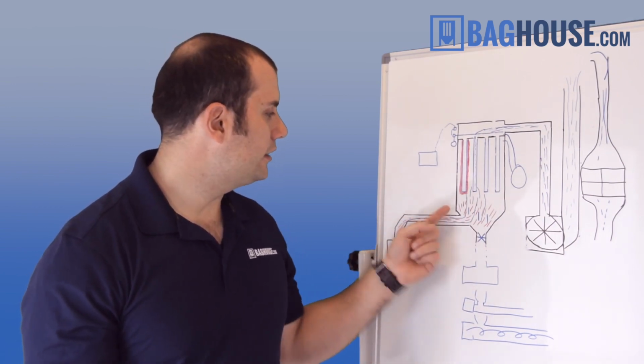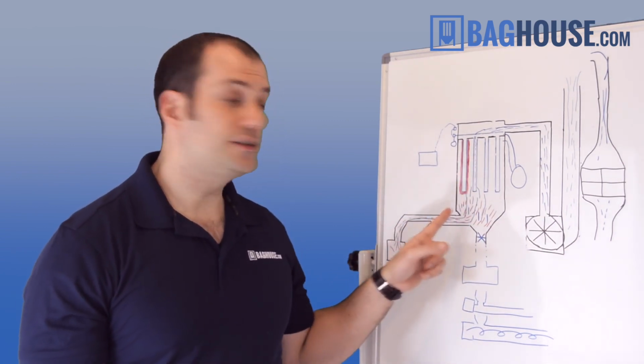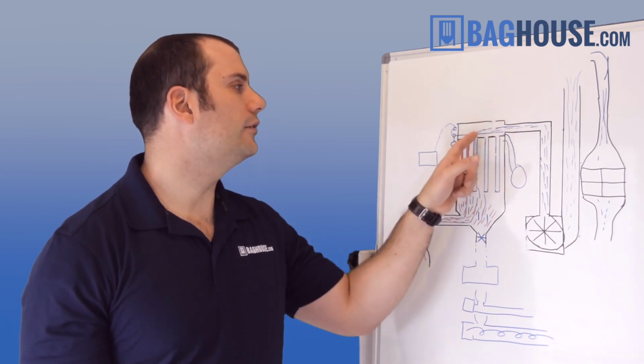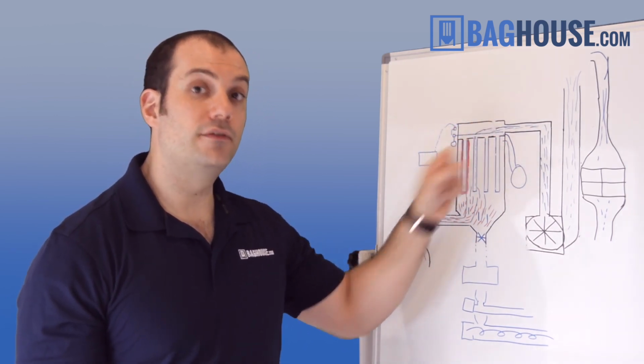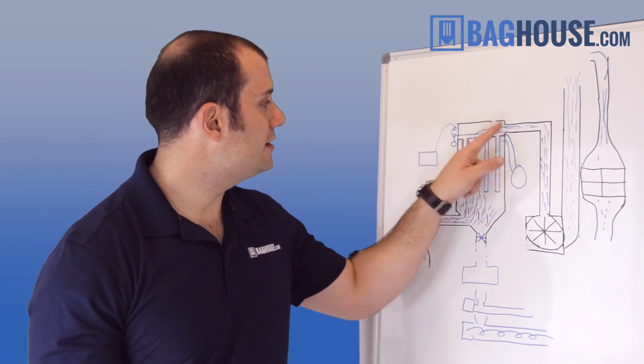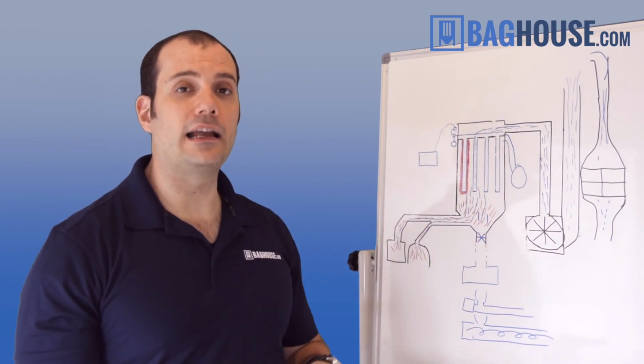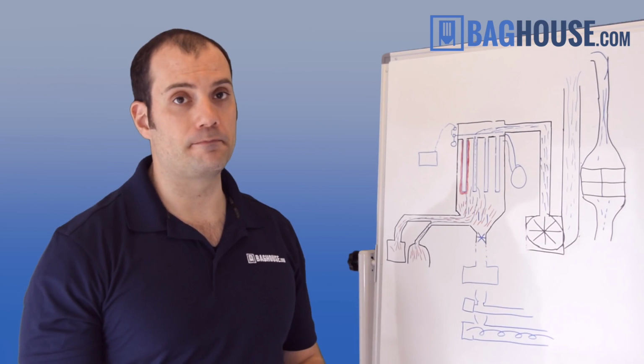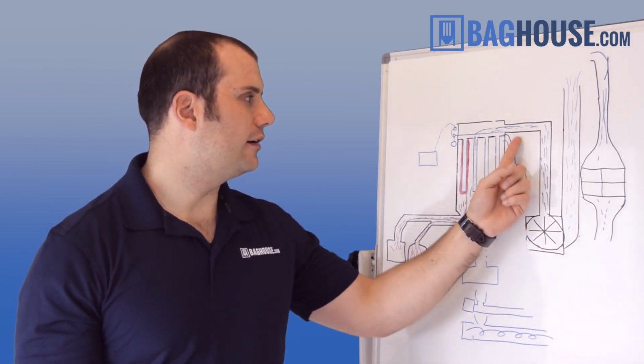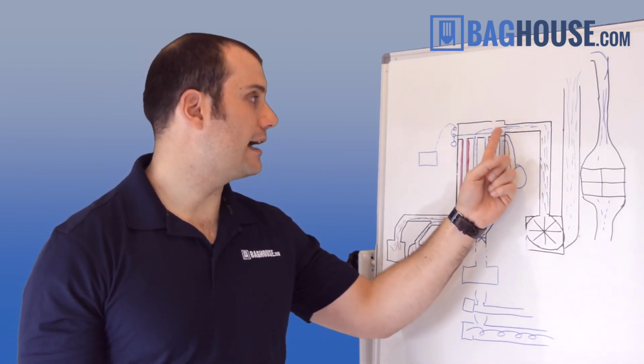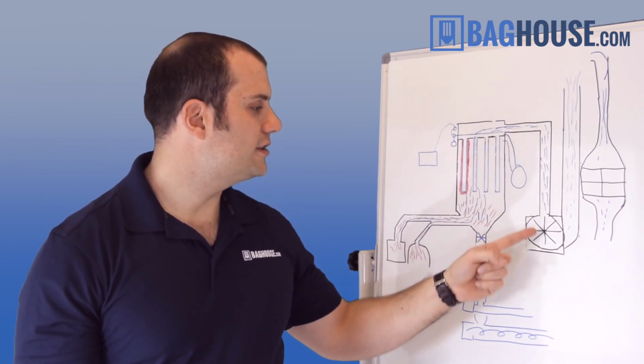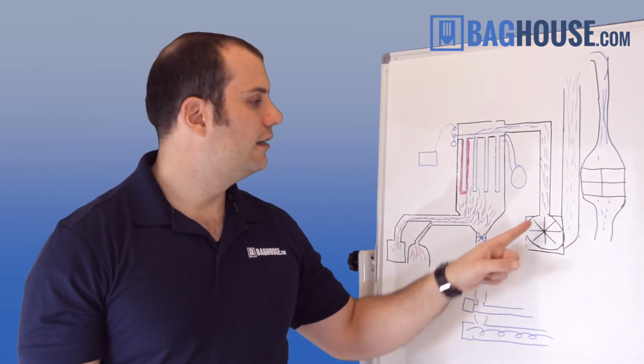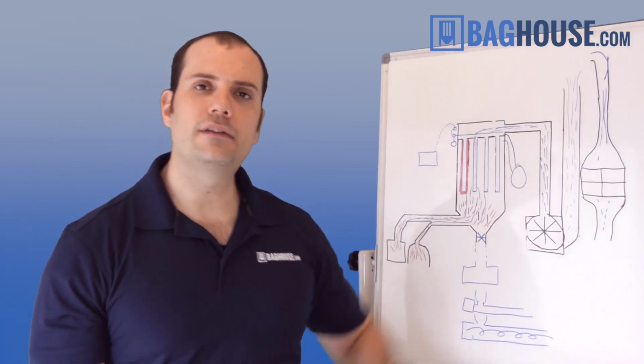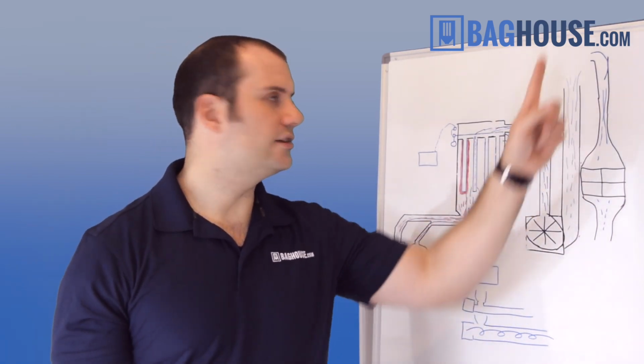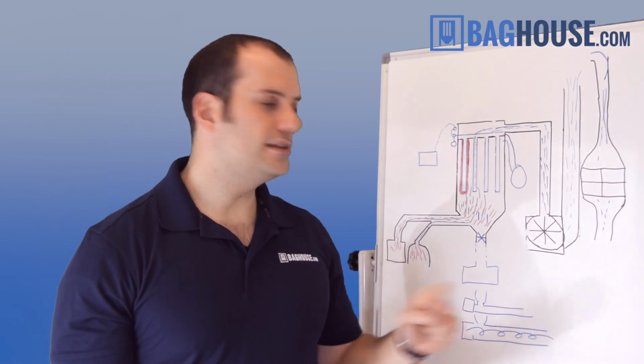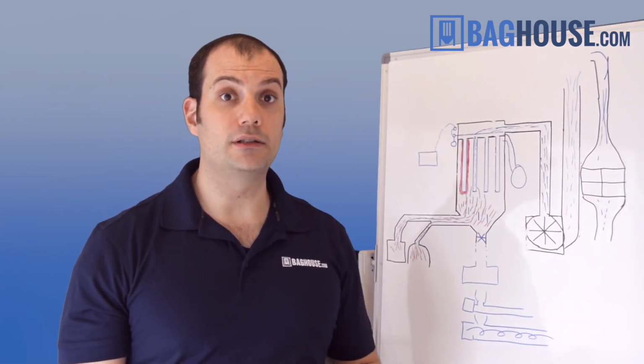Now, as the dirty air comes in, goes into the filters, only clean air comes up and out into this section up here, above the tube sheet. For that reason, we call this section of the dust collector the clean side of the Baghouse, or the clean air plenum. As we leave, we have our connecting ductwork, the Baghouse outlet, that then goes down to our system fan. From our system fan, we then have some kind of exhaust stack that either lets the air exhaust out, or in some instances, we return the air back to the building.